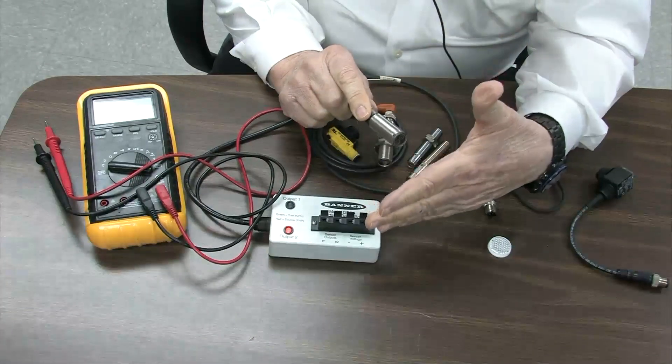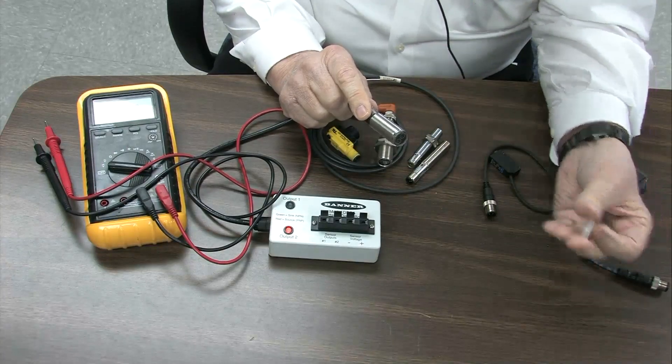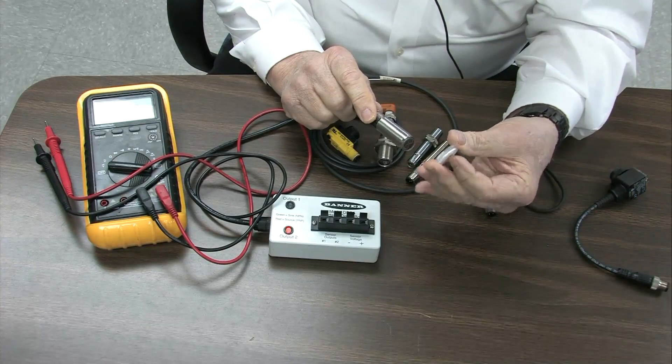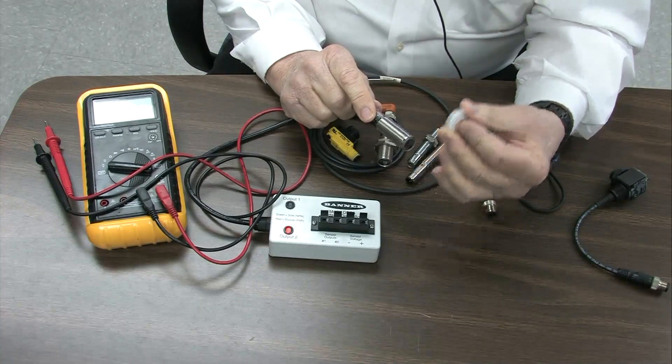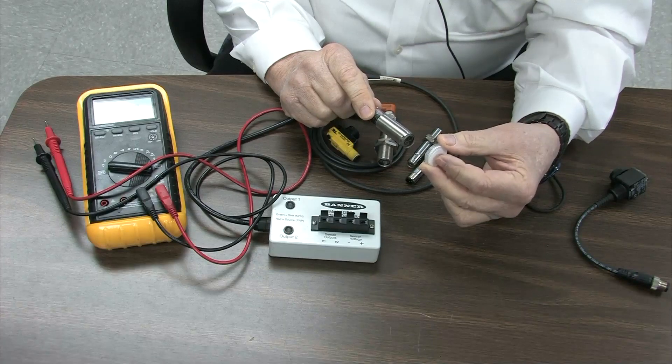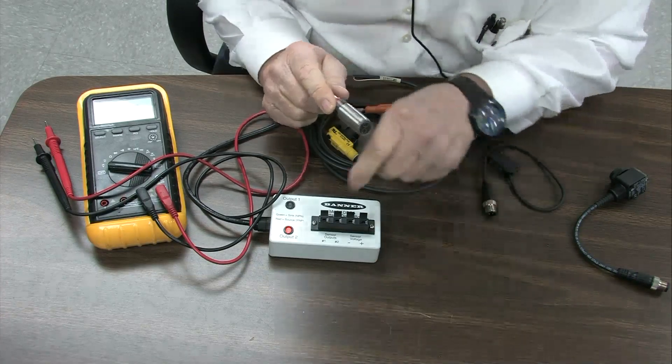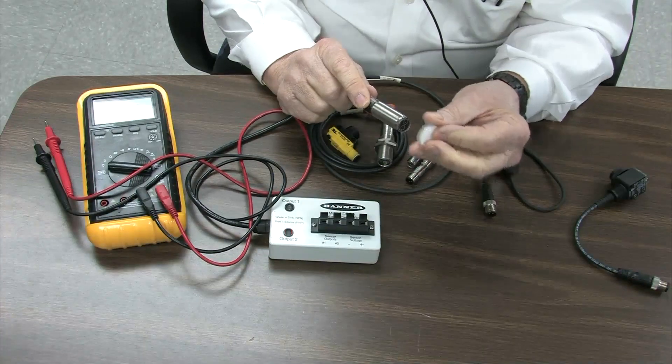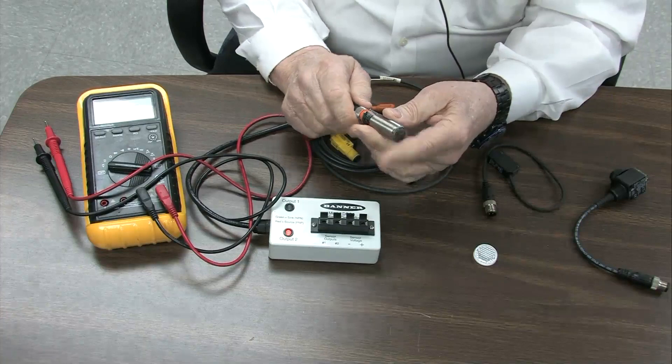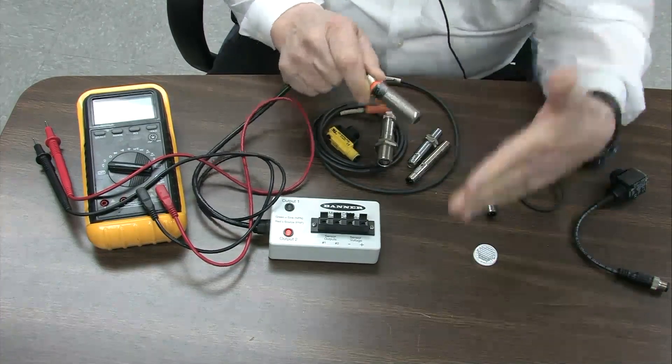I put my hand in front of the sensor, nothing happens, but if I put a reflective device in front of the sensor, output number two is turned on. Output number two, that's this one right here. This is the one that's going to go active. So this device, this particular device works, and you can see the output comes on when there's nothing in front of it.